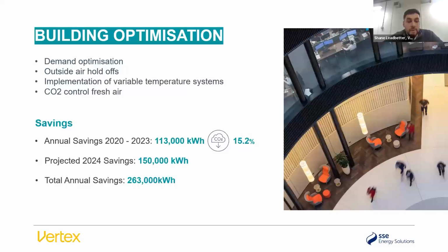We also made use of a variable LTHW system. We already had a variable flow system, but we also implemented a variable temperature system with this. Therefore, the system temperatures would adjust based on the outside air temperature. This would be to maintain efficiency and flow rates.